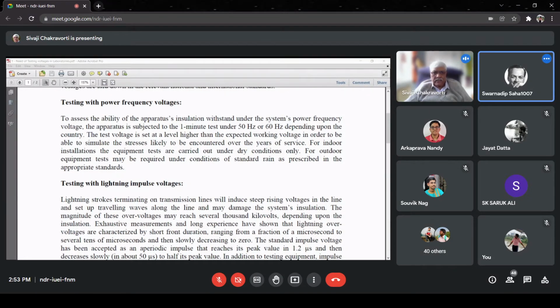Insulation. Exactly. So we are basically testing the insulation, because the failure that occurs because of the higher voltages and the higher field intensities is not for the conductor or the magnetic materials. So it is the insulation that we are going to test.